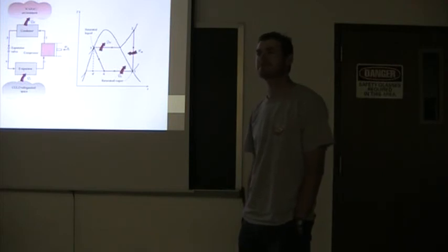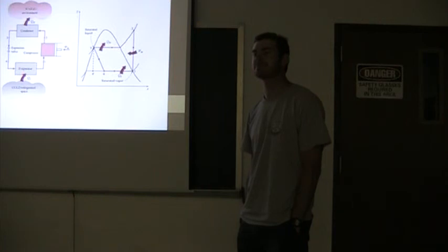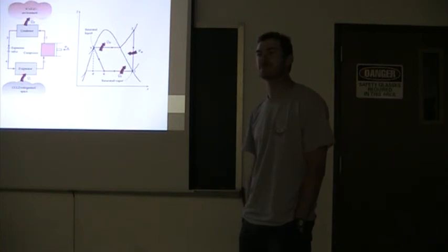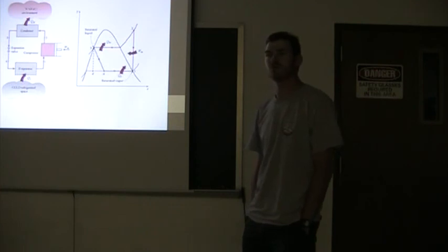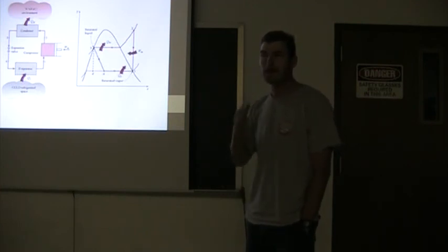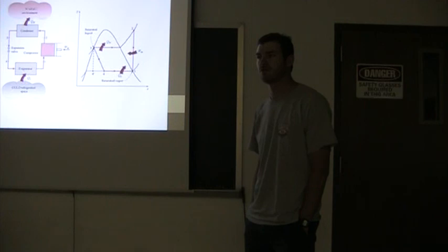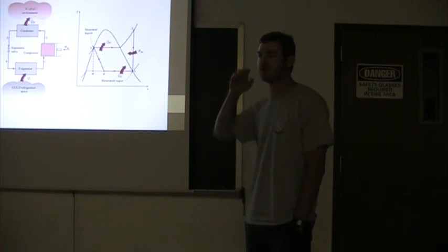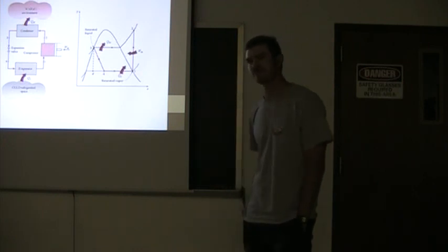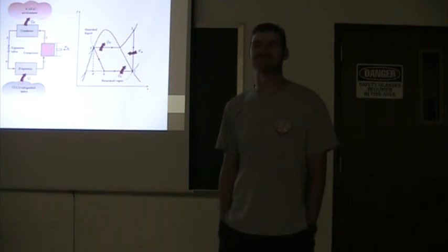I just want to point out the charge level thing again, because we're not adding 13 or 14 pounds. We're measuring the weight before and after turning on the machine, because it's probably only 2 or 3 pounds of charge in it. That's why the coefficient of performance would be lower. Okay, so you had 7.6, right? Yeah, 7.61. A little high. Okay. All right.